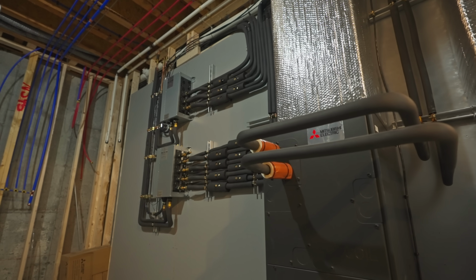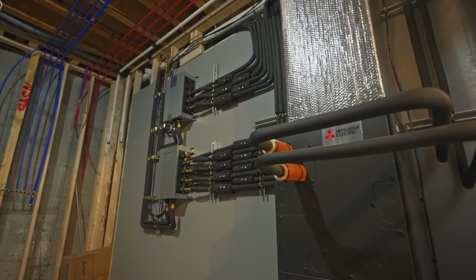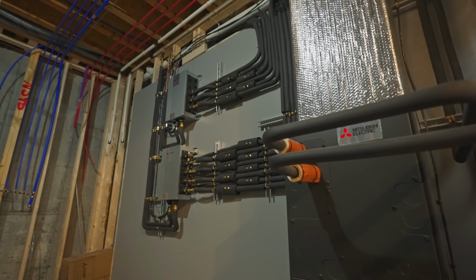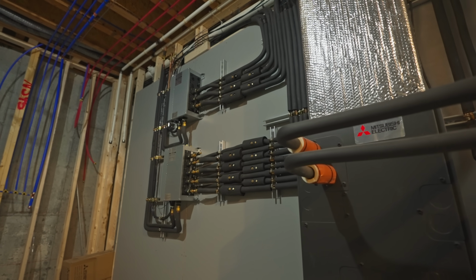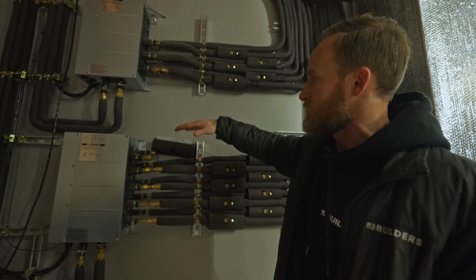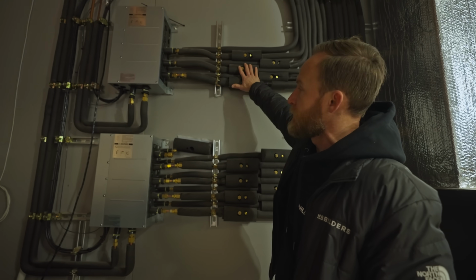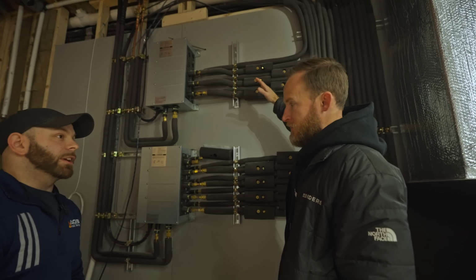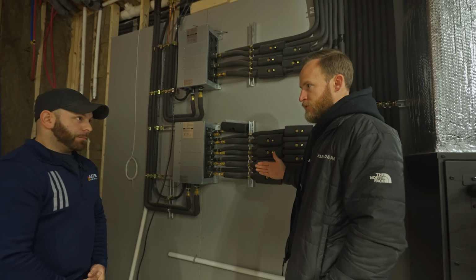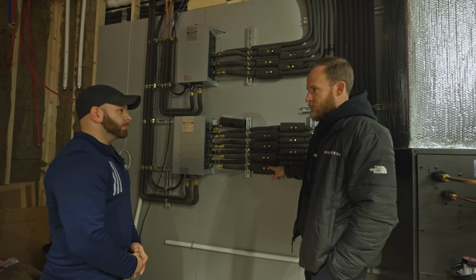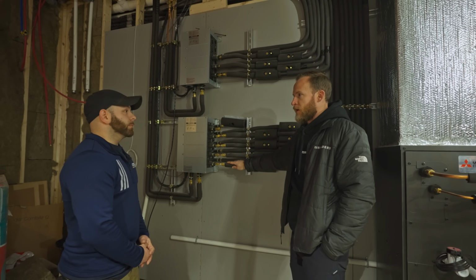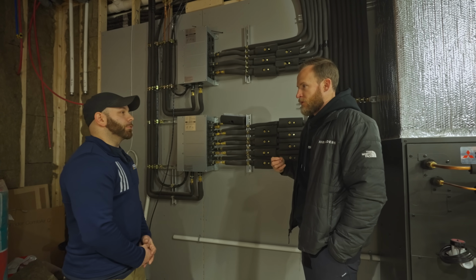We have two branch boxes, tied to your outdoor units, the outdoor heat pumps. So your line sets run from the heat pump to your branch box, and across these two—four here and three here—that makes up our seven indoor units. So if my kitchen has an issue, you can come in and shut my kitchen off. Yep, when you're talking about recovery, you're talking about recovering the refrigerant—pulling the refrigerant right out.